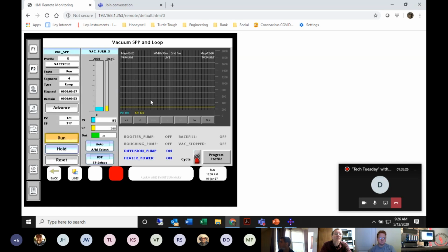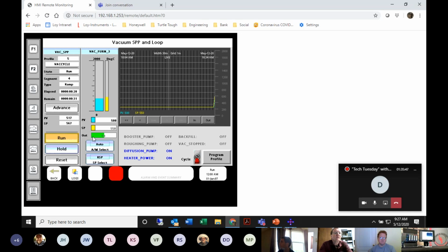Under vacuum set point programmer, the vacuum furnace PID control, which would be VAC furnace 3, this would be an example of a front end of a UDC. So we have our process variable, which is our actual temperature. You can see that ramping up along with set point. We have a percent output. So if you remember, we talked about 0 to 100% output out of a UDC, or the high and low limit is actually -5 and 105%. But in most cases we keep that 0 to 100.